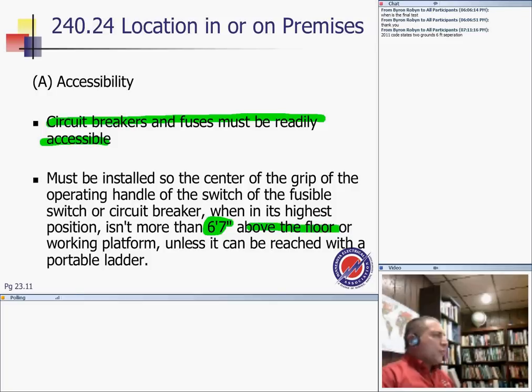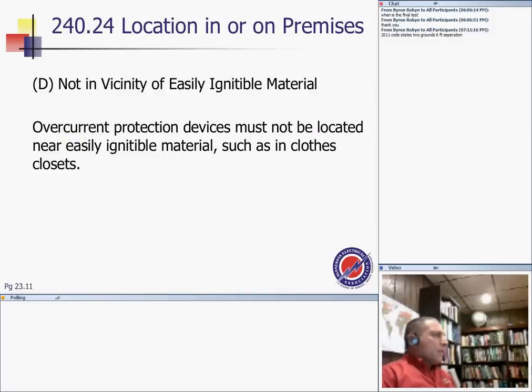When you get your panel situated, you go to the protection device and make sure as you mount your panel, you go from here all the way to the ground. Make sure it's not more than 6 foot 7 inches. That's how they catch you with the inspector. It has to be 6 foot 7 inches from this operating device. Any question, guys, about this? Question about this. So you must not put it in the vicinity of easily ignitible material like clothes.